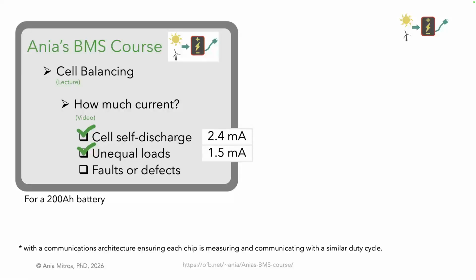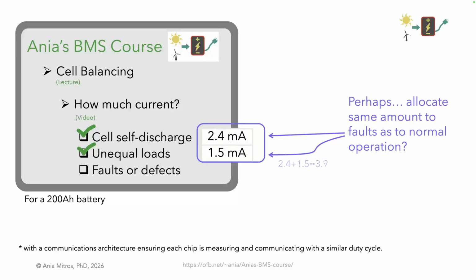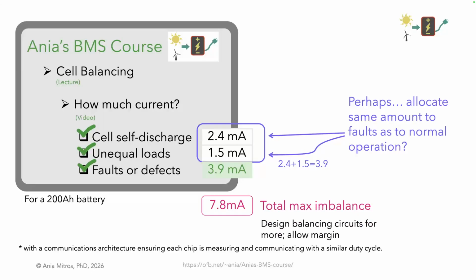So, what do we put for imbalance due to faults? In a perfect world, we'd use data. We'd look at the million units we already have in the field, look at patterns of atypical self-leakage and whether that precedes more catastrophic failure, and decide with knowledge. Without that, maybe we allow the same amount of balancing current for normal effects as to compensate for manufacturing defects. It's somewhat reasonable to allow our error budget to be of similar magnitude as our expected variation. With those numbers, we should design our balancing circuit and controls to compensate for at least 7.8 milliamps of imbalance. I'd recommend a little more. It's always good to have some design margin.